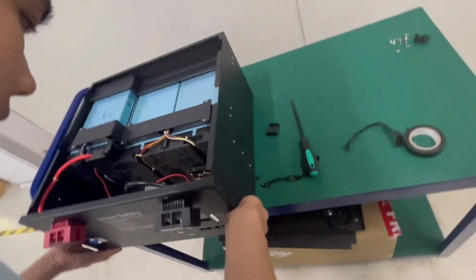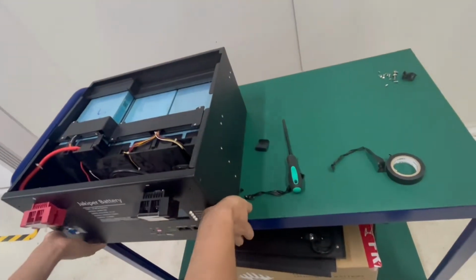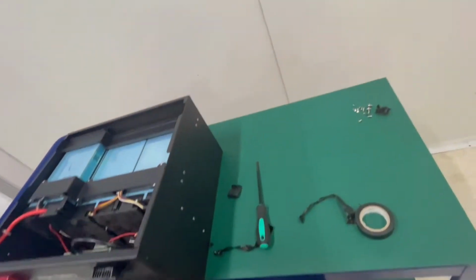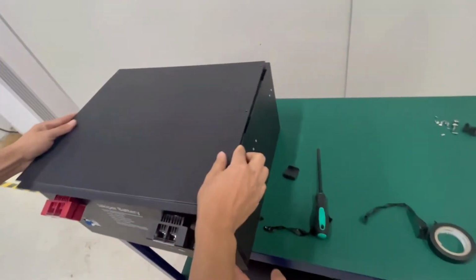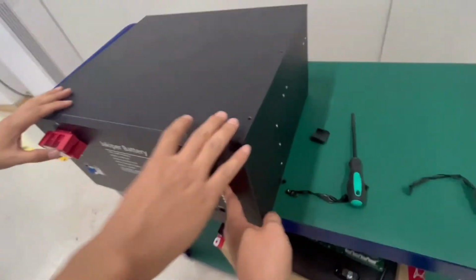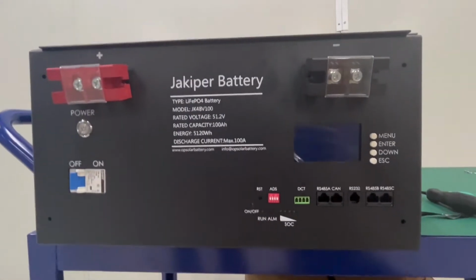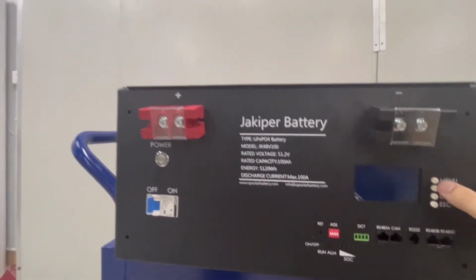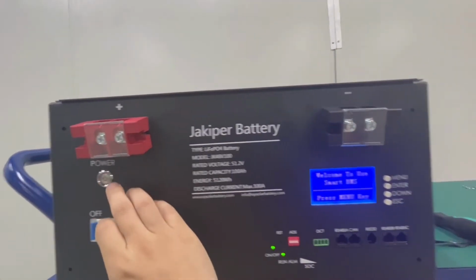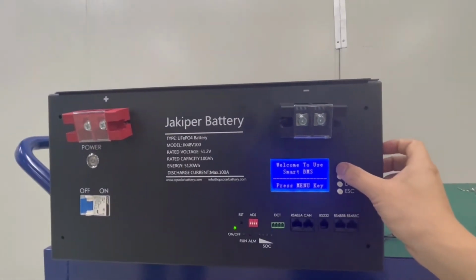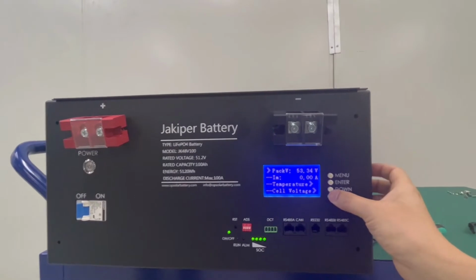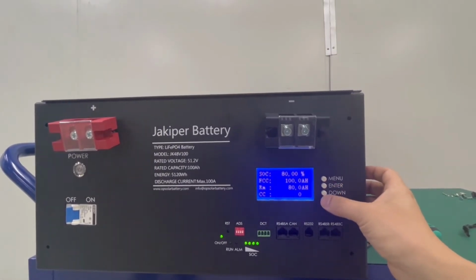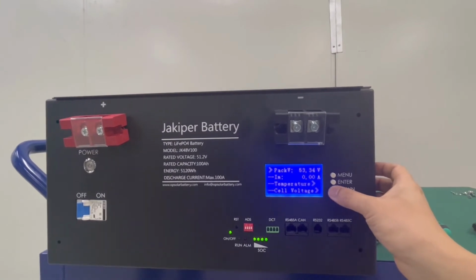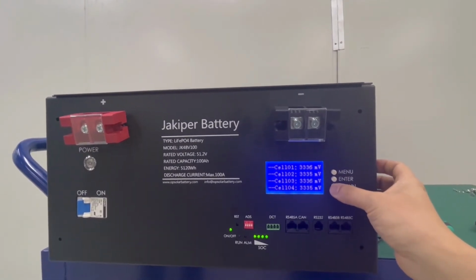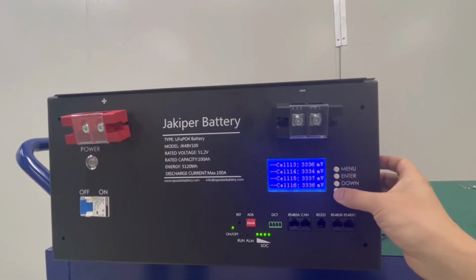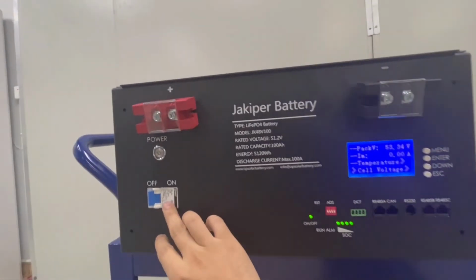Once all the connections are done, you can verify the battery pack condition from the front panel LCD. This front panel comes with our latest design with a power key. To check the function, just press the power key to switch on the BMS, and then you can check the pack voltage from the analog information page - if it's more than 50 volts or not - and you can also check the capacity and cell voltage. If it looks as it did before, then it's working properly, and you will have all the communication options.